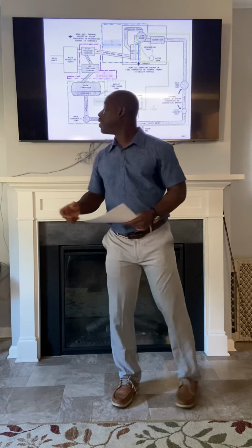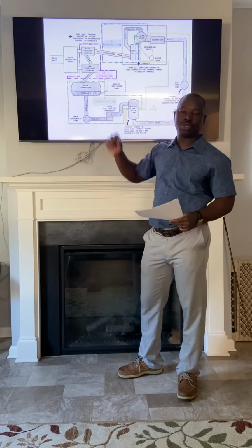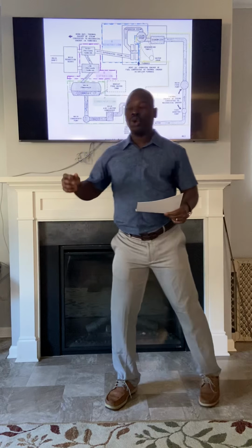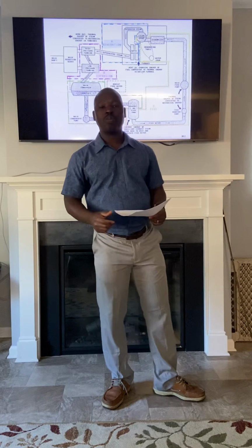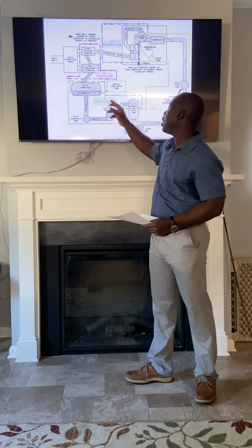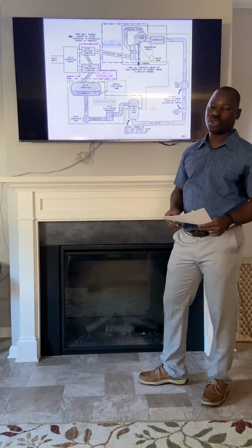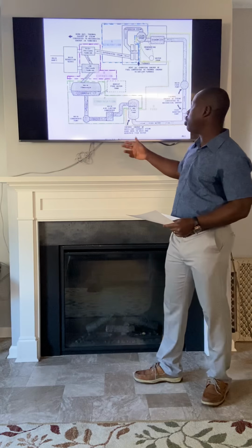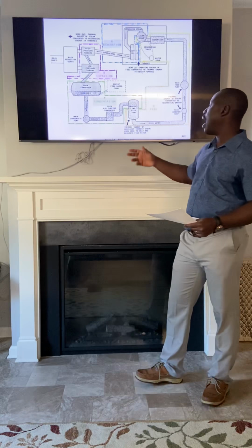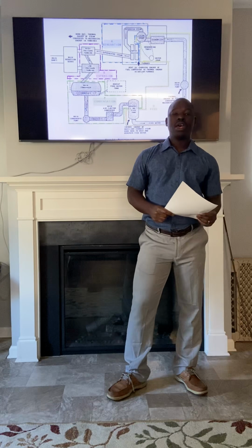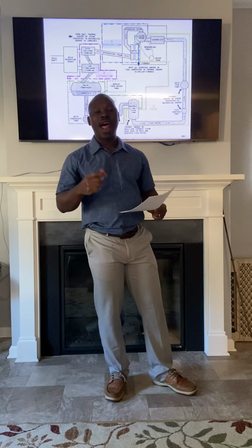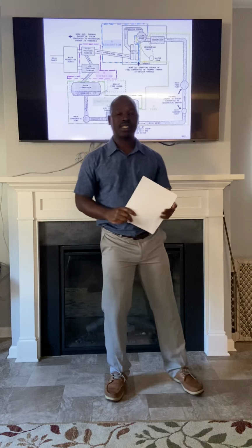The condensate collected in the bottom of the main condenser is removed by the main condensate pump. The main condensate pump sends the water through the air ejector, which removes air and non-condensable gases from the main condenser. Then the condensate continues its path to the feed heater and finally arrives in the deaerated feed tank, which marks the end of the condensation phase. The feed phase is the last phase of the basic steam cycle.